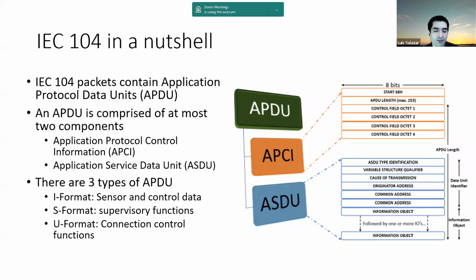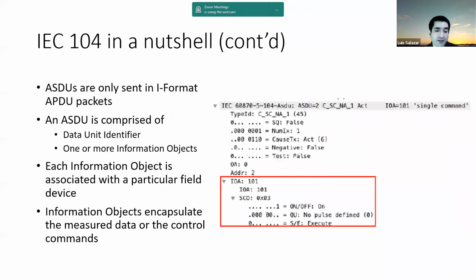So you can have three different types of APDUs. One can be the I format, which is basically sensor and control data that is being exchanged between the SCADA and RTU. You can have the S format, which basically provides a way to have supervisory functions with the RTUs, and the U format, which is just connection control functions between the SCADA and the RTU. Depending on this type, you can have either just the APCI or both the APCI and the ASDU. The ASDU itself is the part of the packet that actually contains the information regarding the power system that you are controlling.